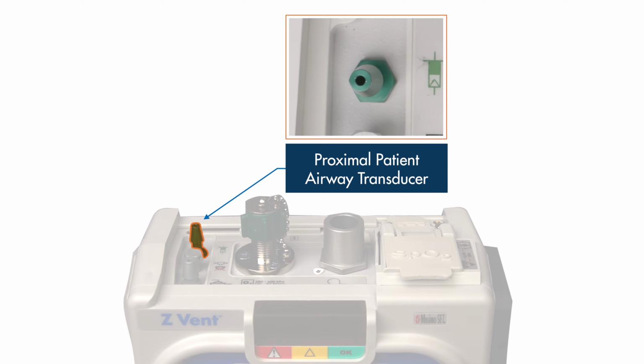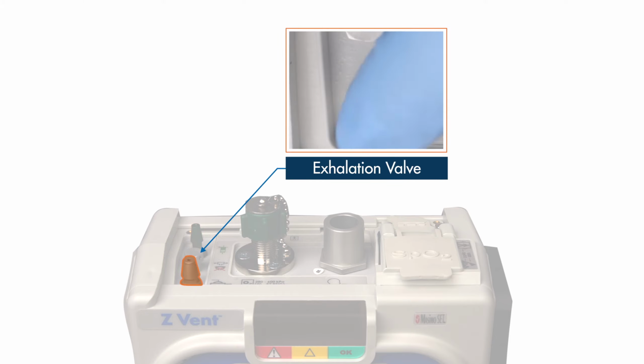Along the left side is a row of 3 ports. The green nozzle at the top left is the patient airway pressure transducer for the patient circuit. The transducer automatically measures airway pressure within the circuit. The silver nozzle at the bottom left is the exhalation valve port for the patient circuit. The Z Vent pneumatically controls the exhalation valve to open or close during inspiration and exhalation, or in the event of an alarm.